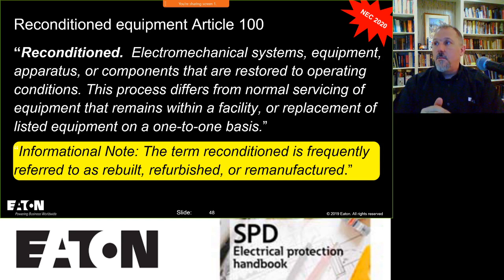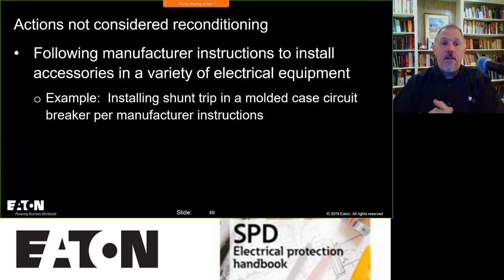And I've had discussions with people, they'll give me examples of what they're doing, and I'll say, well, that doesn't meet the definition. Reusing, I get that all the time. You mean to tell me I can't take a breaker out of my panel board and take it to another facility and use it there? I'm like, well, no, I'm not telling you you can't do that. You can do that. You haven't met the definition of reconditioned. So you're not even into any of the requirements. But if you do meet this definition, then we're going to start talking about 110 requirements and then some of the other sections in the National Electrical Code that tell you whether or not you can or can't.